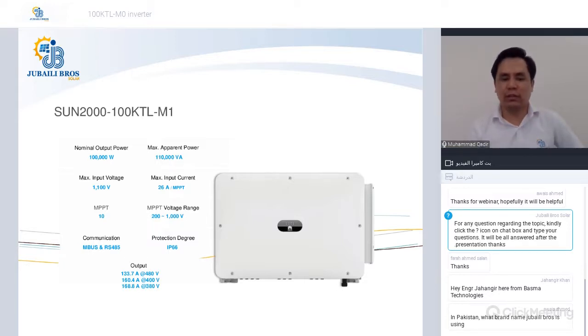Now, the purpose of having 26 ampere per MPPT is to adapt to the new solar module trend, which is higher power, having more voltage and more current. This inverter has 10 MPPTs, which is the largest number of MPPT in any Huawei model. The MPPT voltage range of this inverter is from 200 to 1000 volt, but there is another voltage range called full MPPT voltage range. I highly recommend that whenever you design your PV plants, you look at the user manual and also see what is the full MPPT voltage range, which is around 540 to 800 volt.